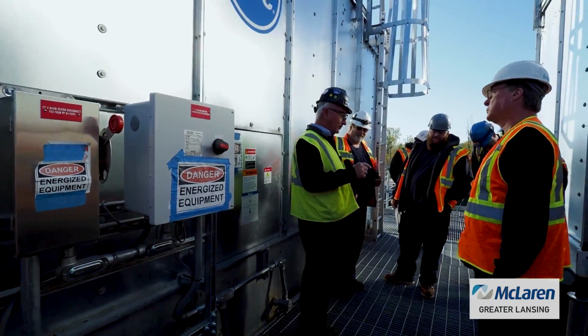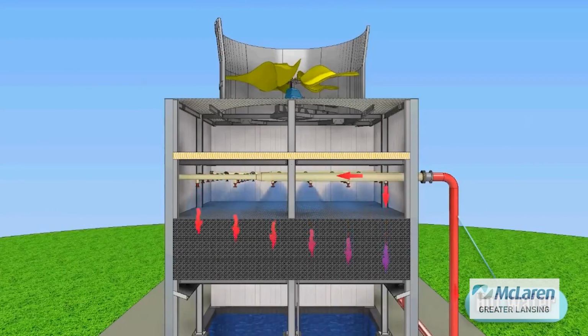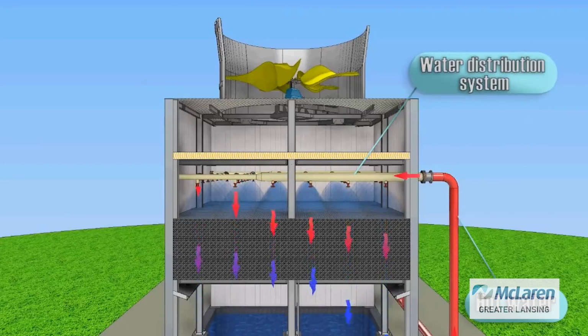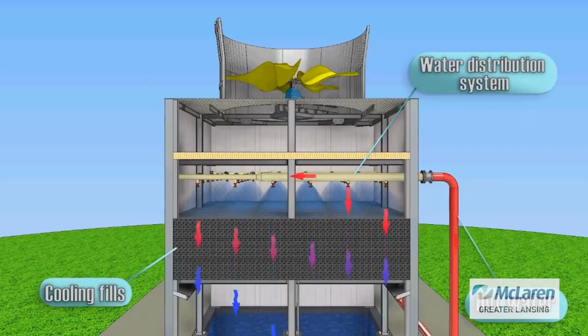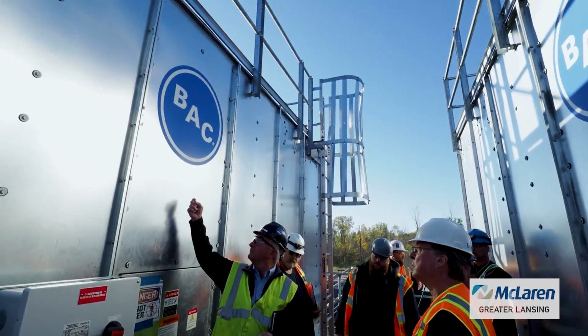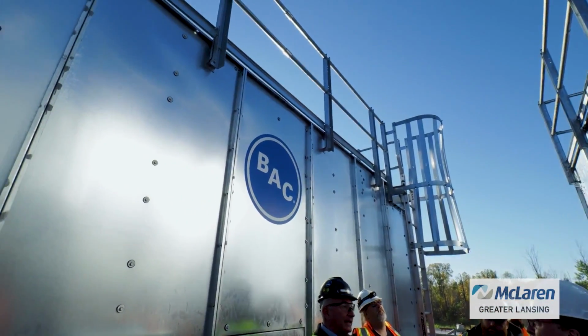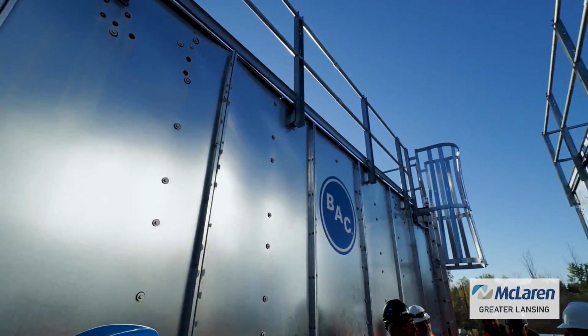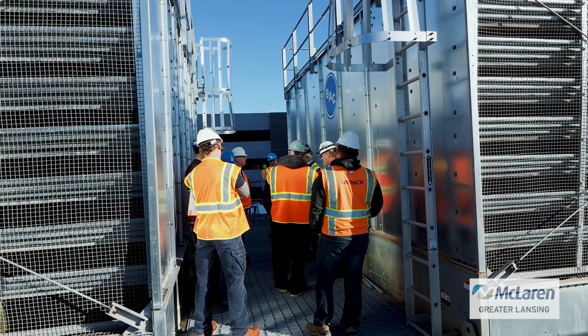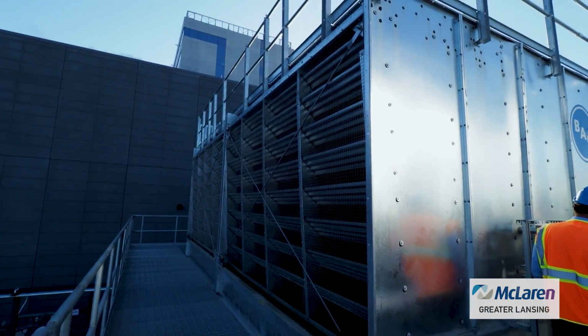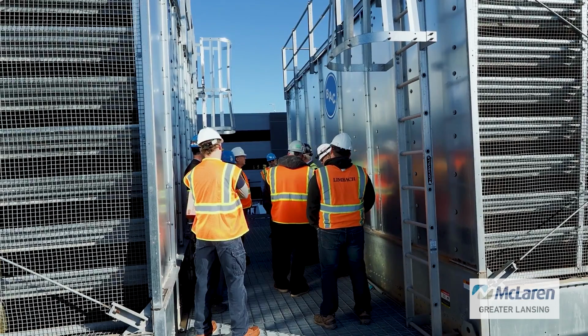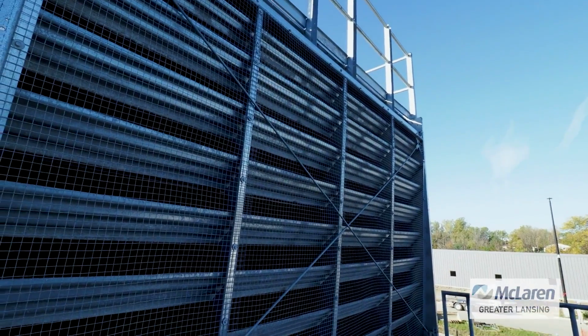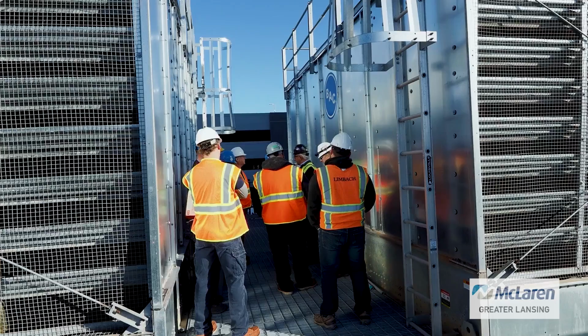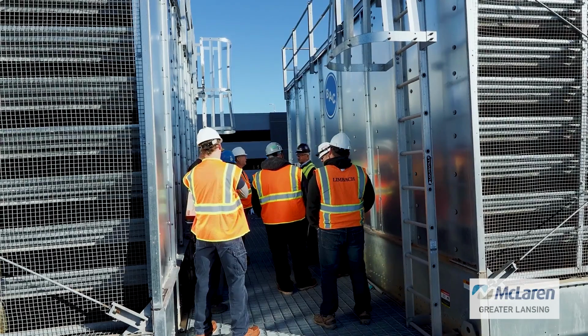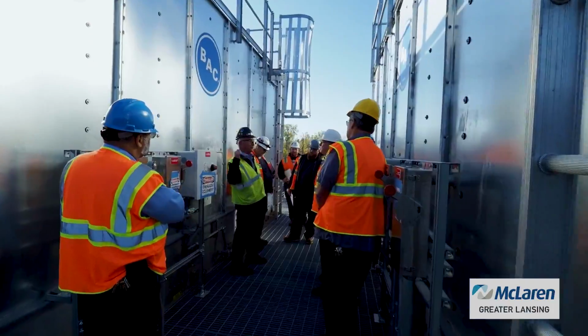So BAC came out with the single inlet piping connection about 92, 93. I'm sitting with a consulting engineer, and it works really great. A much cleaner installation, but what you have is symmetrical piping from here, so you end up with balanced flow. The overhead piping, there's an expense to that. There was another installation where 3 cells just like this, design build, but the contractor took some shortcuts. The piping ran all the way down into 1 cell, no valves, none, 0. And I about crapped a brick. I thought, how are you getting balanced flow on cell 1 and cell 3? Detect any difference in level in the hot water basins from one tower to the other.